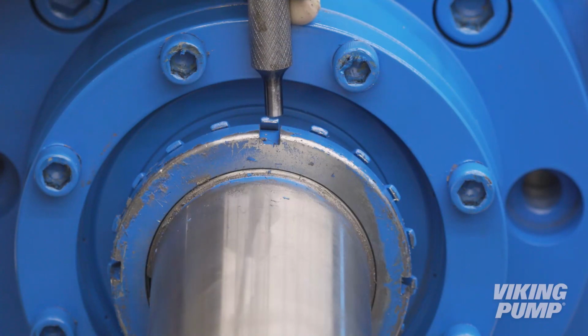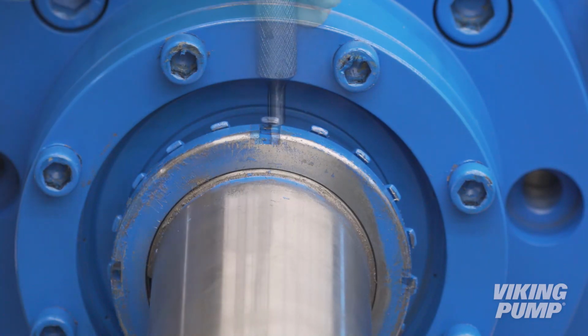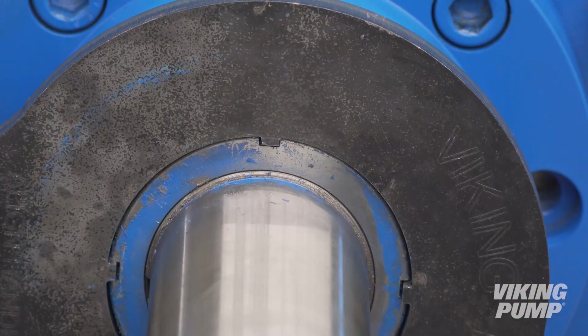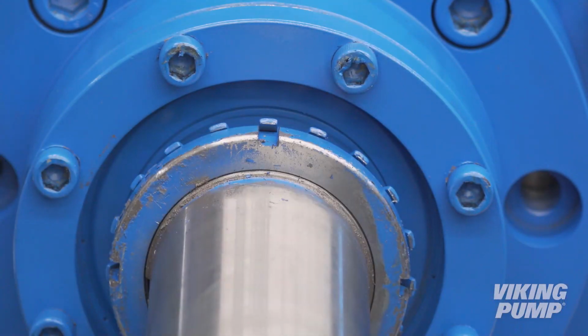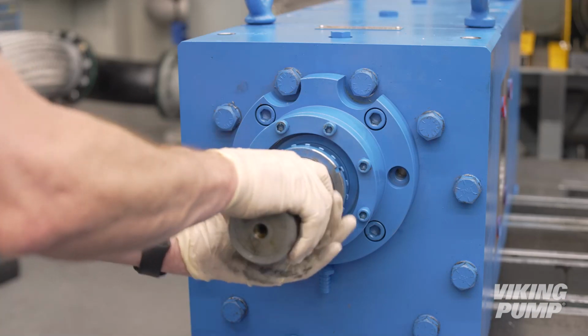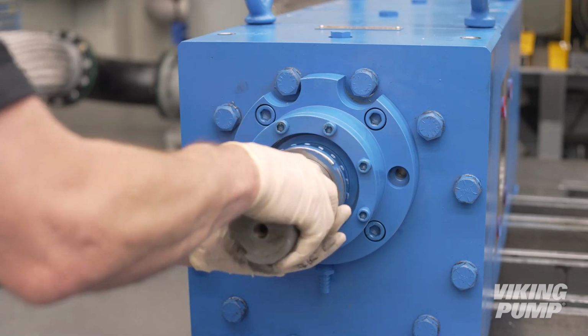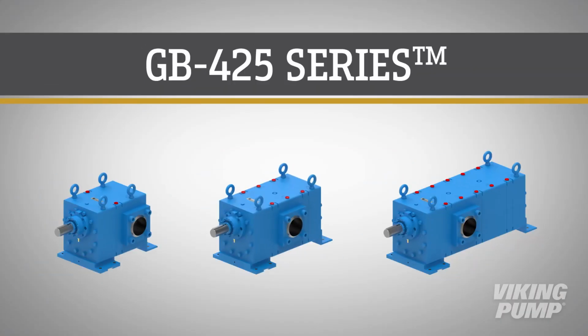Finally, bend a tang of the lock washer that aligns with the groove of the lock nut. If no tang aligns, tighten until one does. Finally, turn the shaft manually to ensure the pump rotates smoothly. Your Viking Pump GB-425 series pump is now fully rebuilt and ready to be put back into service.